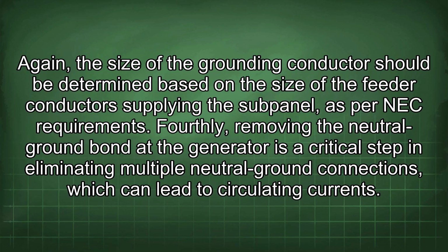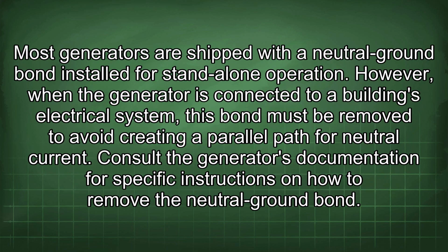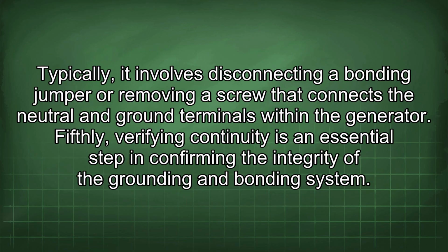Fourthly, removing the neutral ground bond at the generator is a critical step in eliminating multiple neutral ground connections, which can lead to circulating currents. Most generators are shipped with a neutral ground bond installed for standalone operation. However, when the generator is connected to a building's electrical system, this bond must be removed to avoid creating a parallel path for neutral current. Consult the generator's documentation for specific instructions on how to remove the neutral ground bond. Typically, it involves disconnecting a bonding jumper or removing a screw that connects the neutral and ground terminals within the generator.